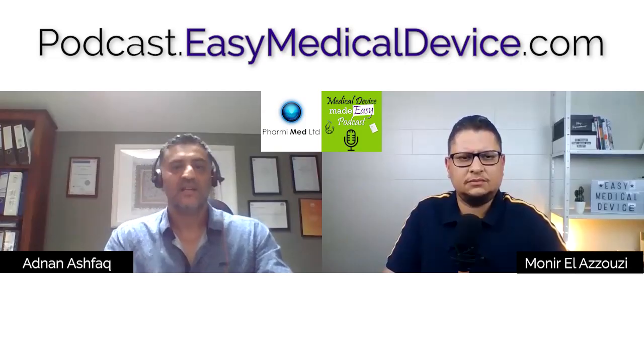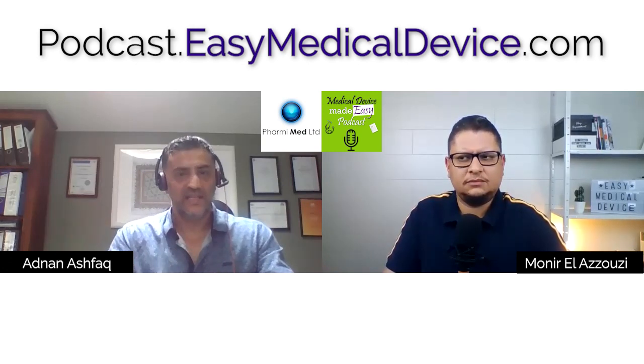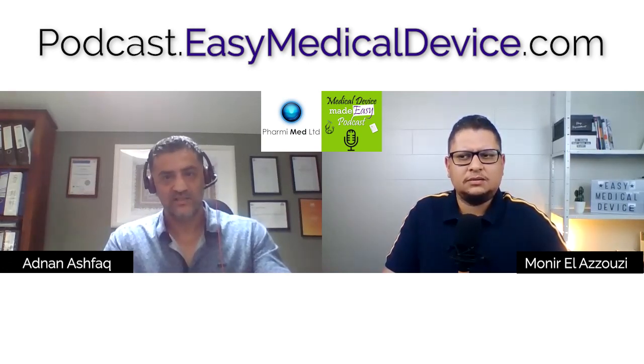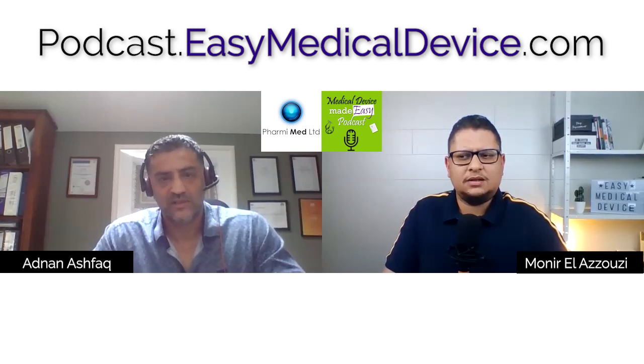And then what you need to do is ask some questions. And the questions are based on risk. And if you look at the hazards from the risks that the software can create, it can then be declassified to a B or an A. B meaning that it can lead to a minor injury, non-serious injury, and A, it can lead to no injury. So there's a slight differentiation, different classification.